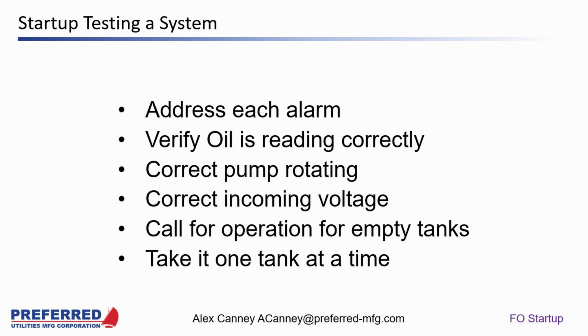The biggest thing about taking it one tank at a time is that you verify that you are going to the correct tank. If your system says tank 1 is filling up, but all of a sudden you see tank 3's level going up, then you know that somehow the wiring got messed up. And that may not be obvious from just a control side, which is why it's important, if you're in the same area, to be monitoring manual level gauges, things like that, maybe an access port of some kind. But if you're not in that area, be in communication with somebody via radio or cell phone or something like that, who can verify that the tank is filling, but also something like high level. I know for myself, there have been situations where if we're testing a high level switch, I have to ask myself the question, what if this doesn't work? We're testing it for a reason, right? So if I'm just looking at a control screen, I might not be able to see that in time, but being able to see it in person or have somebody observe it.